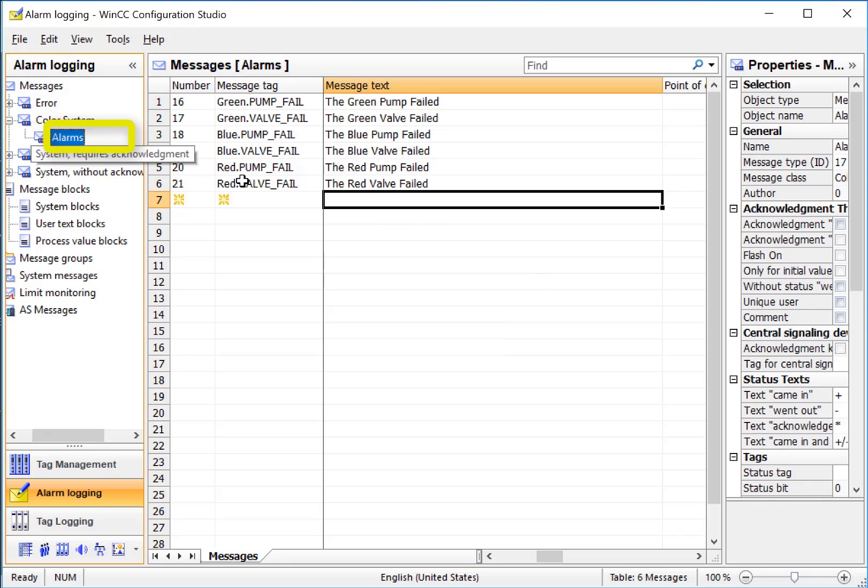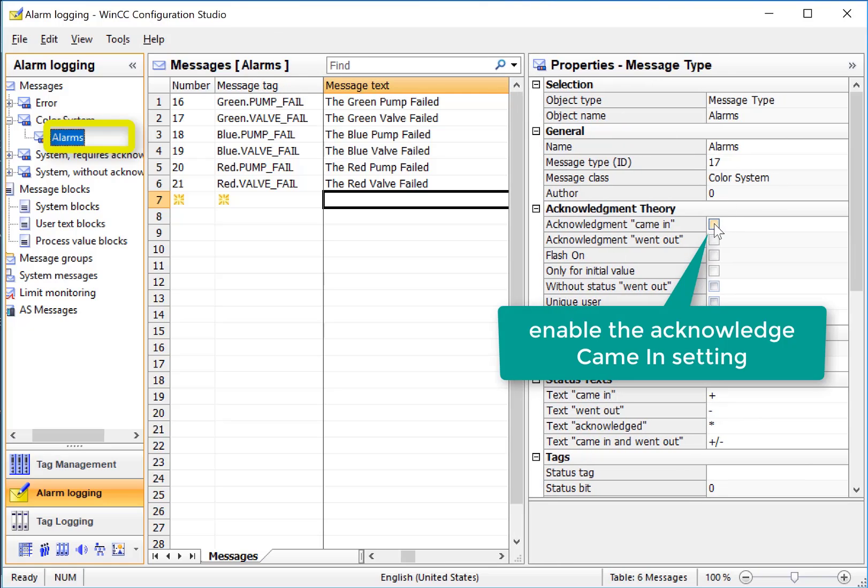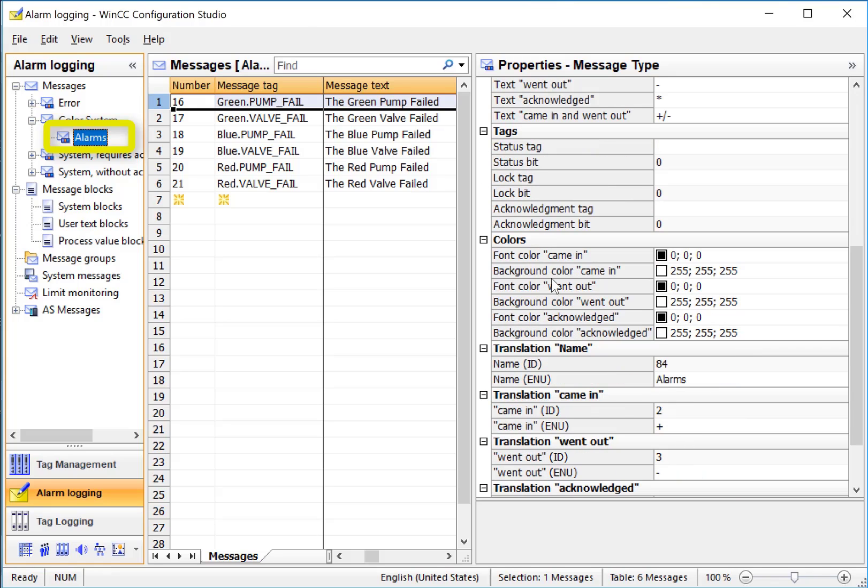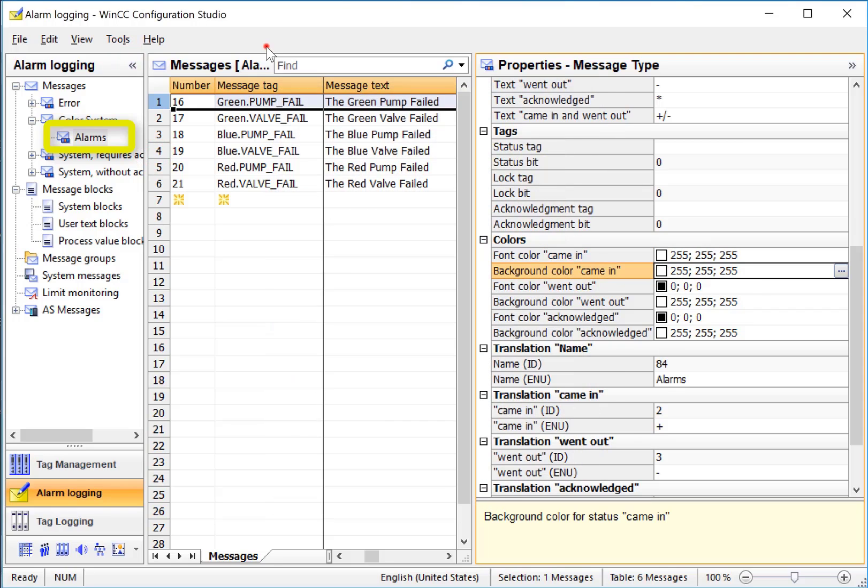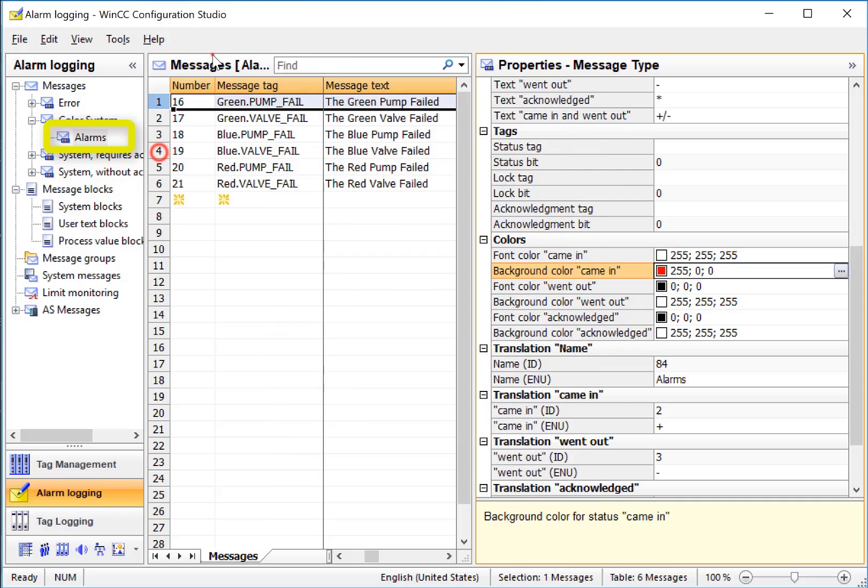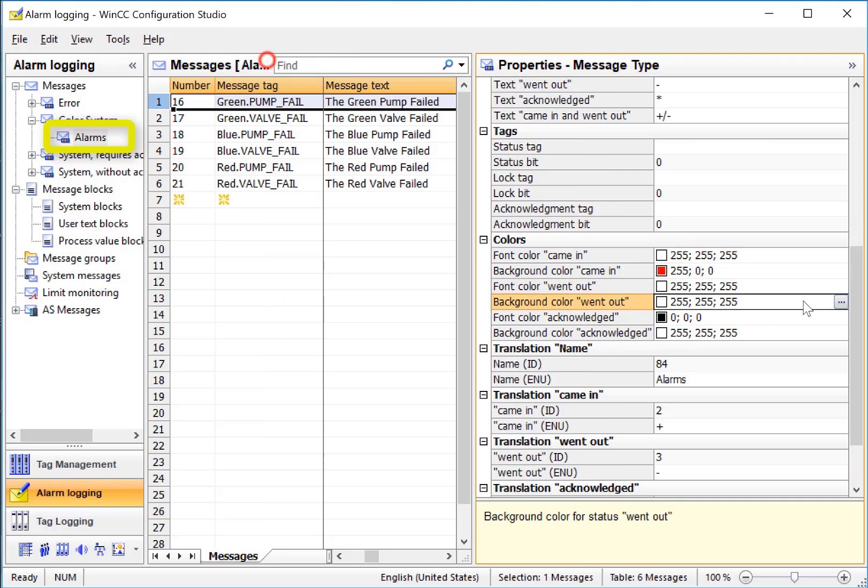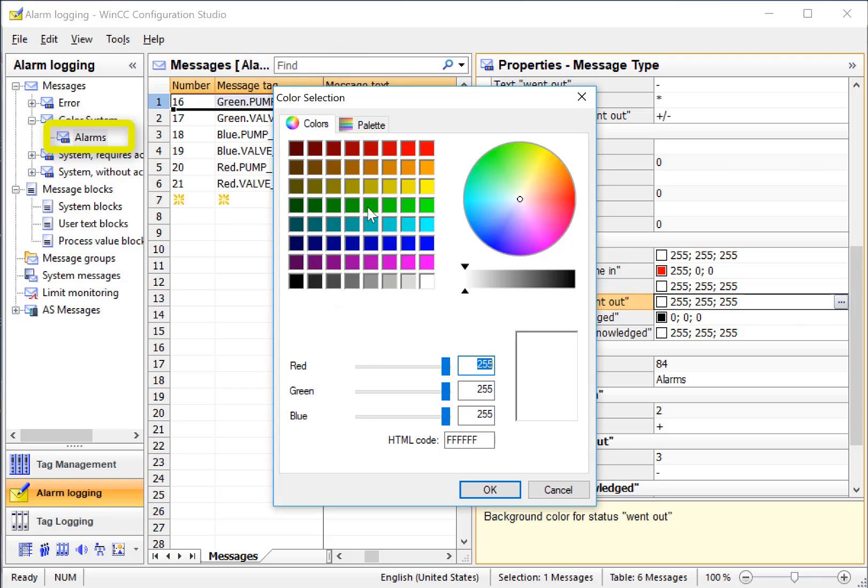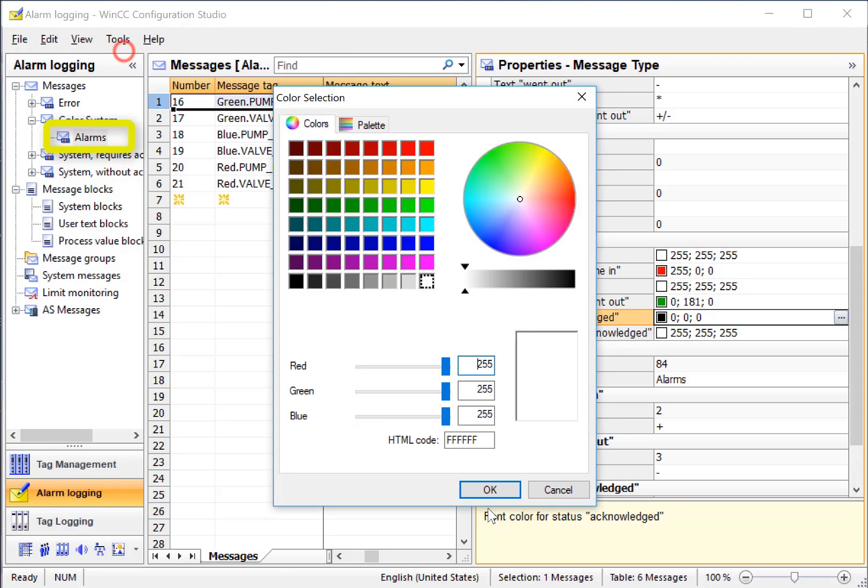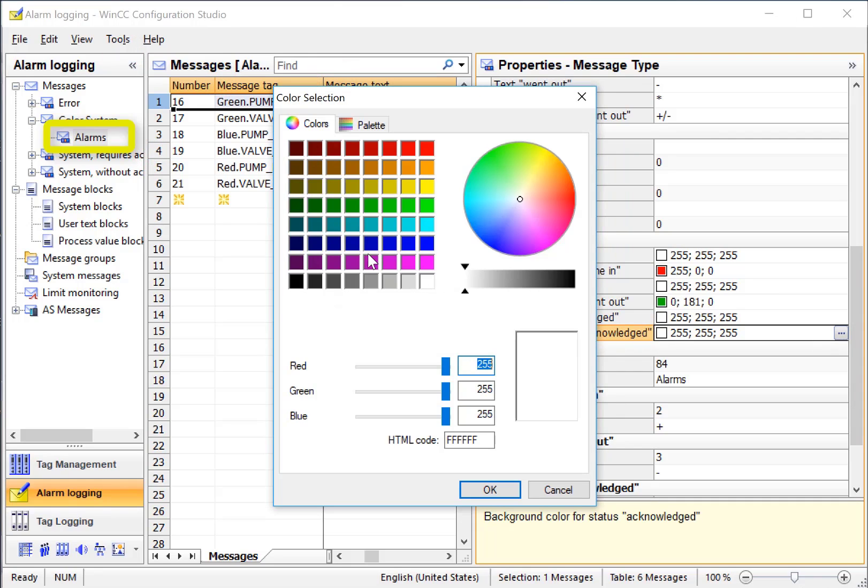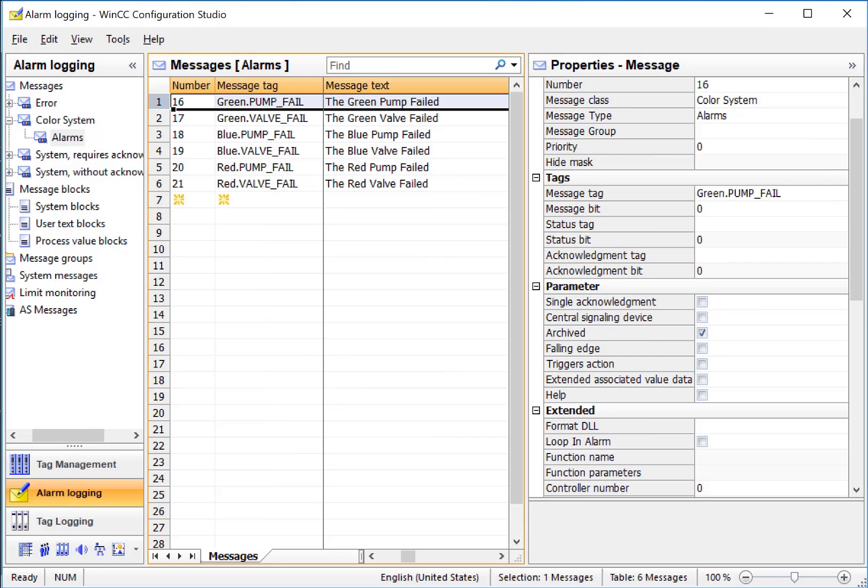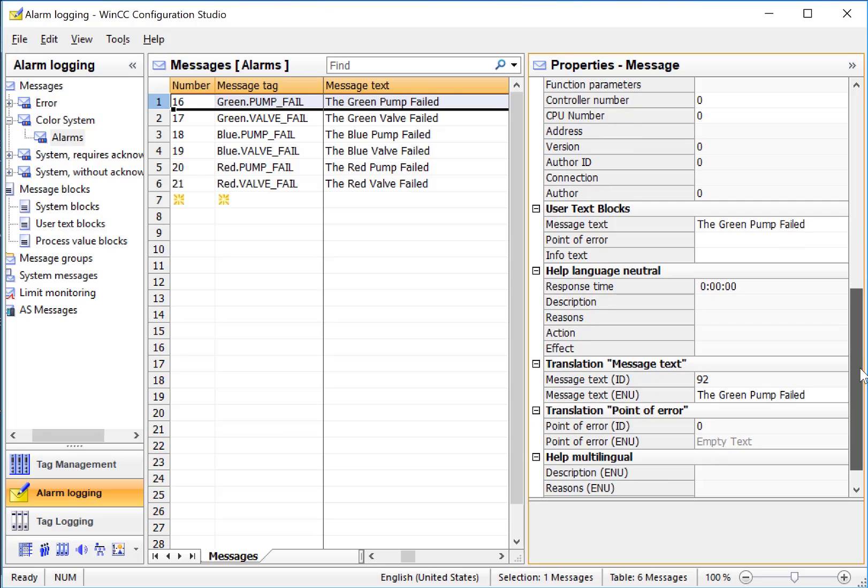Now going back to look at the properties of our subclass, we can define that these alarm messages that belong to the alarm subclass must be acknowledged by the user. We will also want to set our colors for the different states of alarm. We have came in, went out, and acknowledged. So for the font color, we'll choose white, and then the back color of the alarm coming in, we'll choose red. For going out, we'll set the font to white, and the background color to green. For acknowledged, we'll set the font to white, and the background to blue.